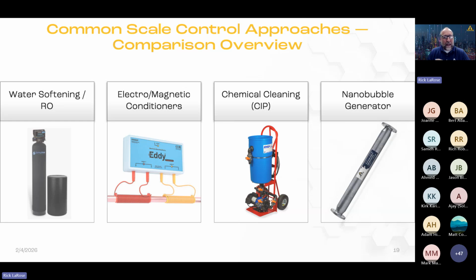This is not a replacement for your Rydlyme cleaning. It's not something where, if your heaters are completely scaled up with no flow through them, you slap a nanobubbler on and in three hours it's clean. No, I'm going to tell you to do a CIP with Rydlyme and clean it up first. That's not what this is designed to do. It's designed to take a clean system and keep it clean.